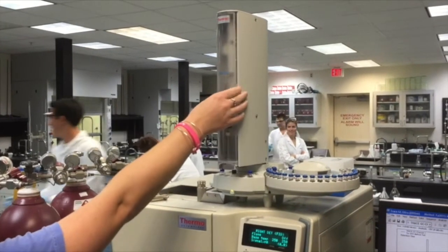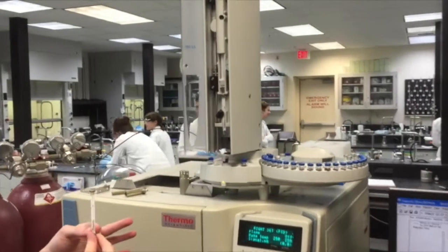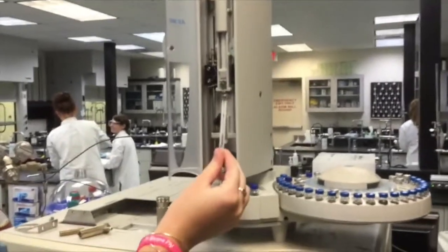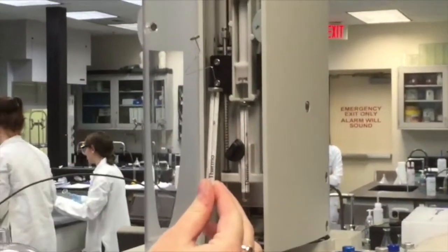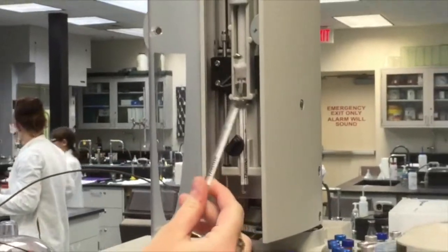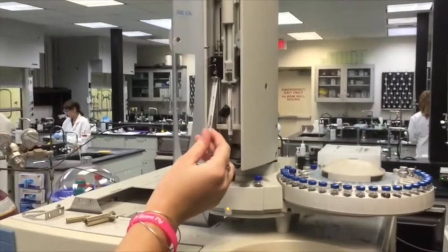In addition to checking the gases, you also want to check the needle because it can get bent up, or we call it Z'd. So you see the one on the left is definitely Z'd, it's messed up, and you want to make sure that the needle in there doesn't look like that.